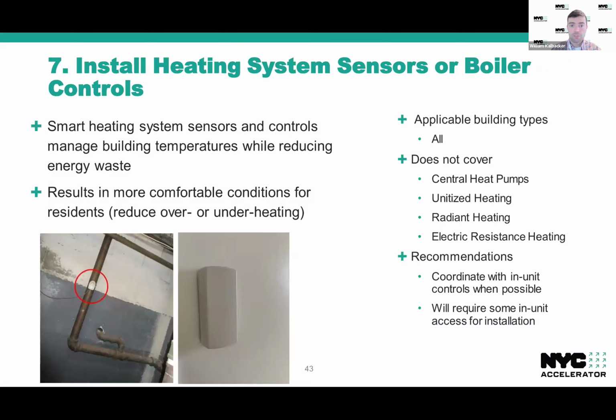So measure number 7 is to install heating system sensors or boiler controls. The central systems in a lot of buildings require sensors for feedback to determine whether they have sufficiently heated the building or not, so they can learn when to turn off and not overheat the spaces. And the philosophy here is that if you have a smart system that can tell what the temperature is outside as well as what the temperature is inside, then you're going to be minimizing your energy use and reducing energy waste. And it's going to be more comfortable for residents overall.